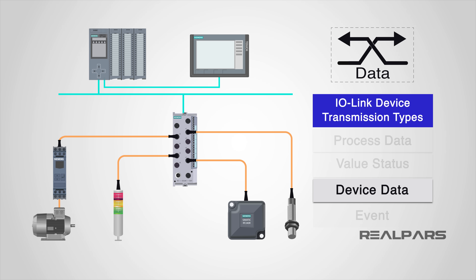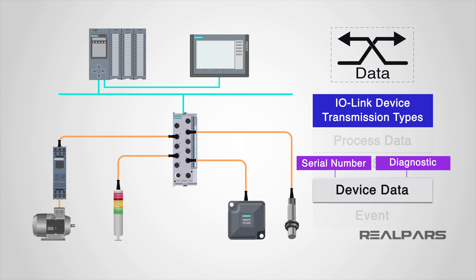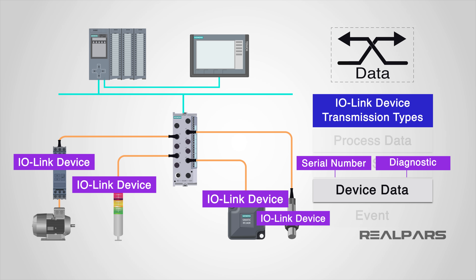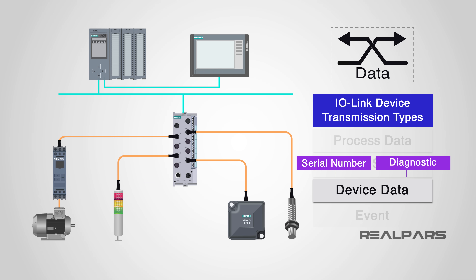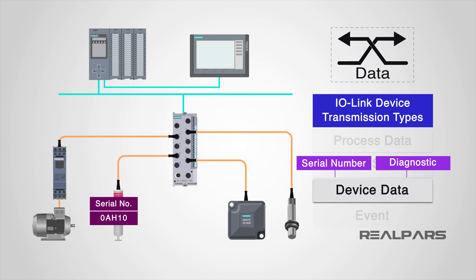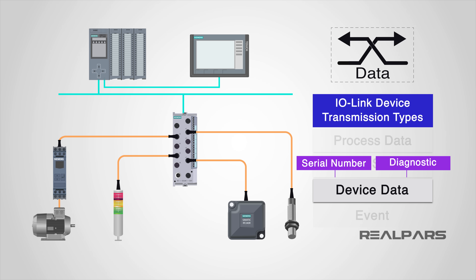The device data holds detailed information about a device. Basic information, such as the serial number or version number, and more advanced information, such as parameters or diagnostic information, are able to be retrieved from each IO-Link device. The device data is transmitted acyclically at the request of the IO-Link master, meaning it is not automatically transmitted but will be transmitted after a request from the IO-Link master. Device data can be read from the device, but also written to.